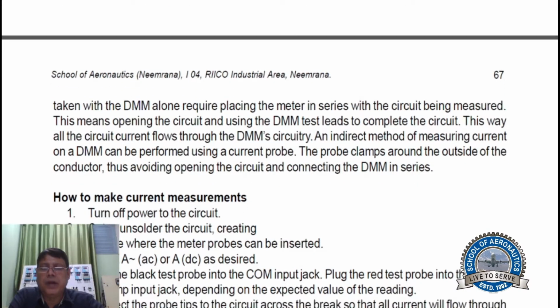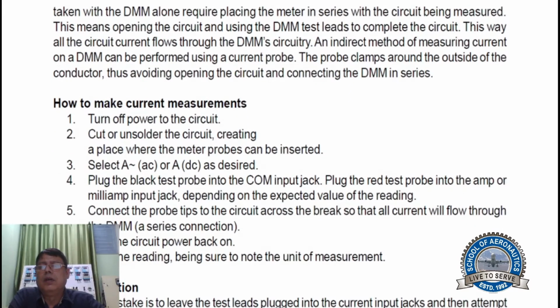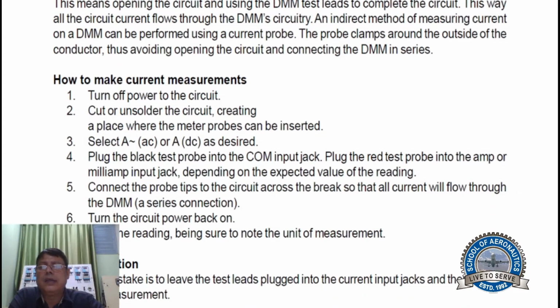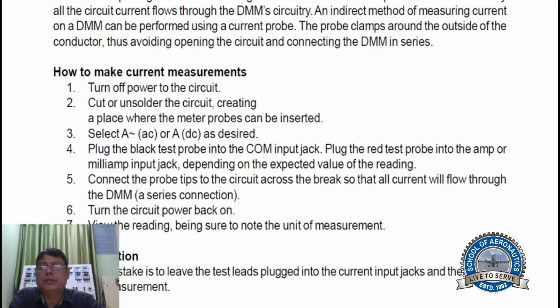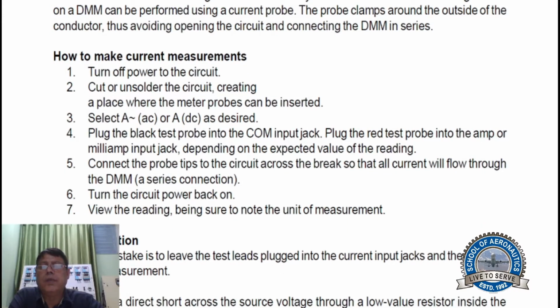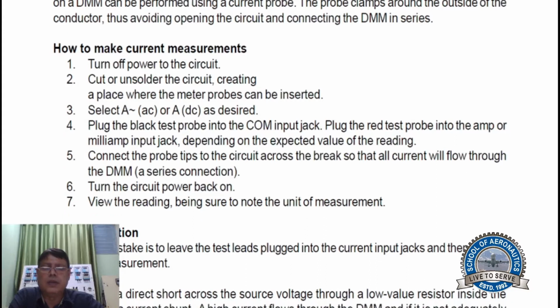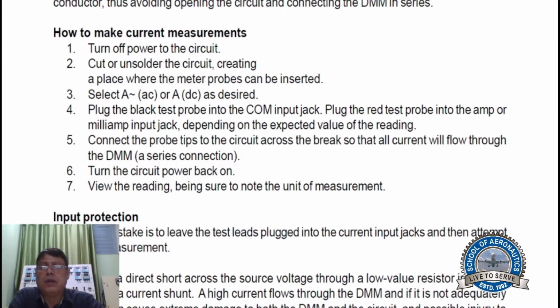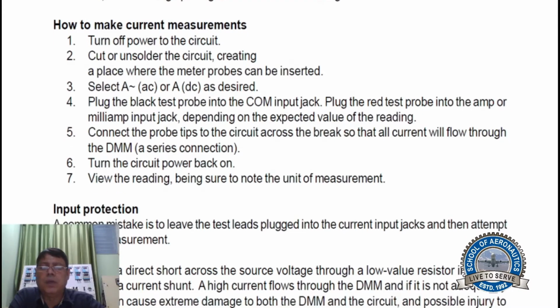How to make a current measurement? Turn off power to the circuit. Cut or unsolder the circuit, creating a place where the meter probe can be inserted. Select A AC or A DC as desired. Plug the black test probe into the COM input jack. Plug the red probe into the amp or milliamp input jack, depending on the expected value of the readings. Connect the probe tips to the circuit across the break so that all the current will flow through the DMM, a series connection. Turn the circuit power back on. View the reading, being sure to note the unit of measurement.